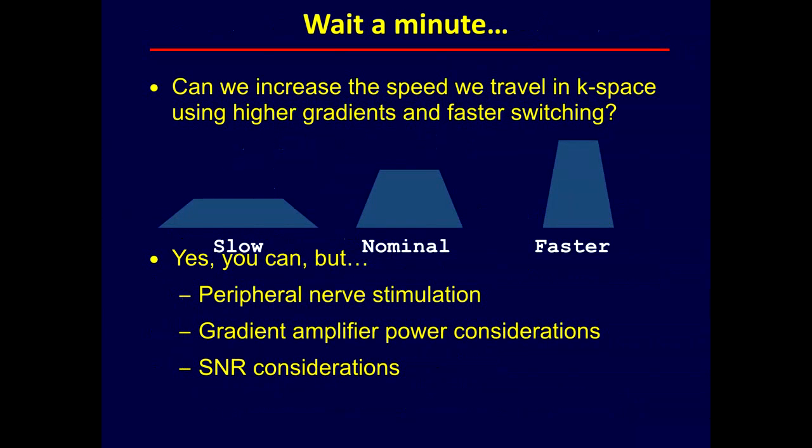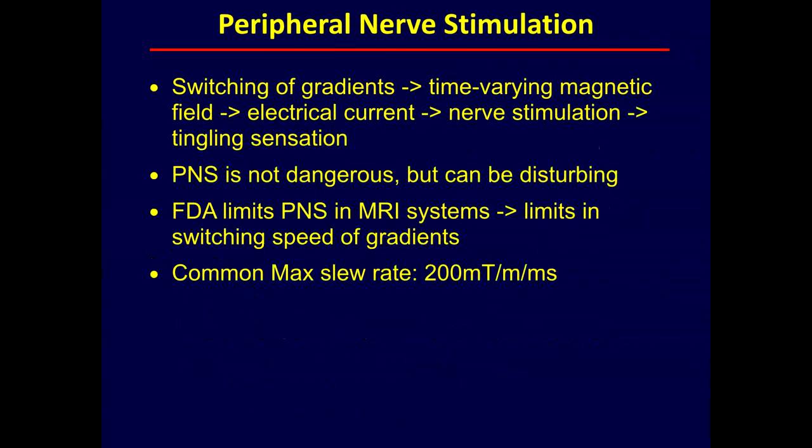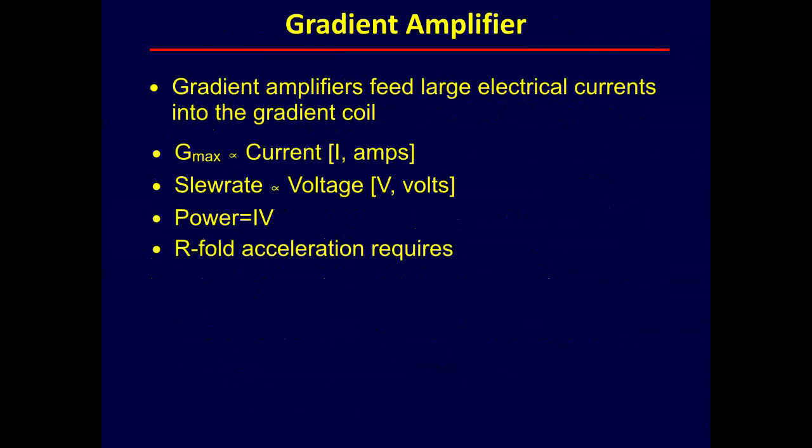I'm going to skip here. Basically, these just tell you that to make the MRI faster, there's only so much you can do with making faster gradients because of limitations in SAR and peripheral stimulation. I hope you have heard of these two terms. Okay, peripheral stimulation is the stimulation of your nerves, and it determines how fast you can ramp up the gradients. And for the maximum gradients, there's an energy limitation, because you cannot make the gradient amplitude infinite. There has to be some limit there. So there are very tight limits, and there's not so much you can do. I'm going to skip all this because I think you all know this. The alternatives, which are today's topic, are parallel imaging and compressed sensing.